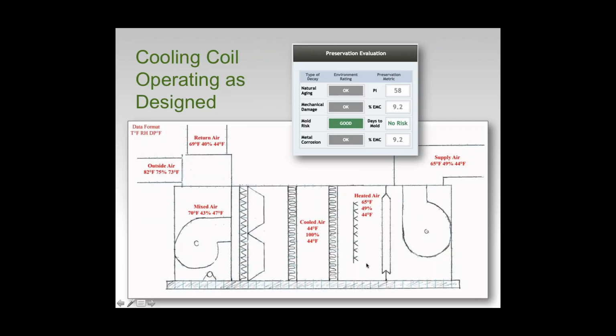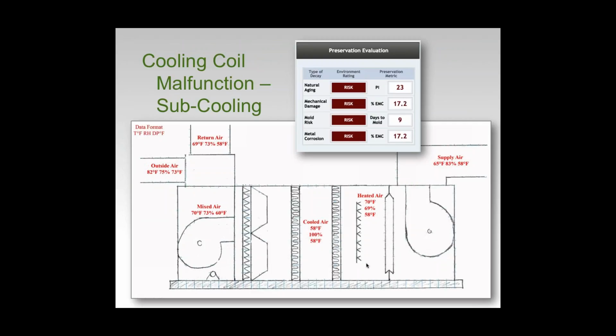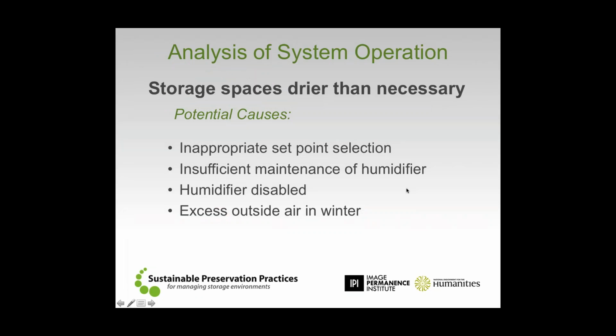Now, what's going to happen if we go into this particular circumstance and realize that we just messed up on the cooling side, and now all of a sudden our cooling coil doesn't have the same amount of capacity that it did before? Maybe we lost our chiller, maybe the chiller malfunctioned, or maybe we have poor flow through the cooling coil. So at the back side of the cooling coil, we wind up with 58 degrees. That's what's going to determine our dew point. Now we send that out at that 58 degree condition at 100%, and we've got this issue where by the time we get back out to the space, we see far too high of a relative humidity condition.